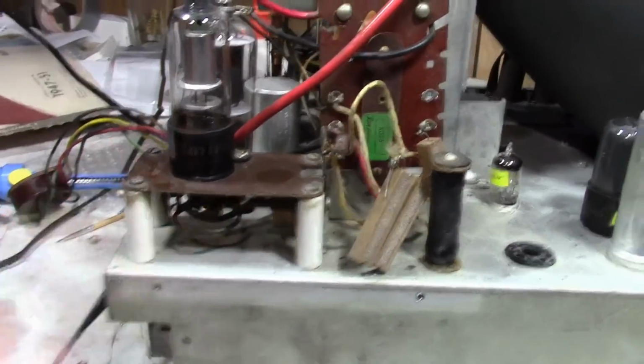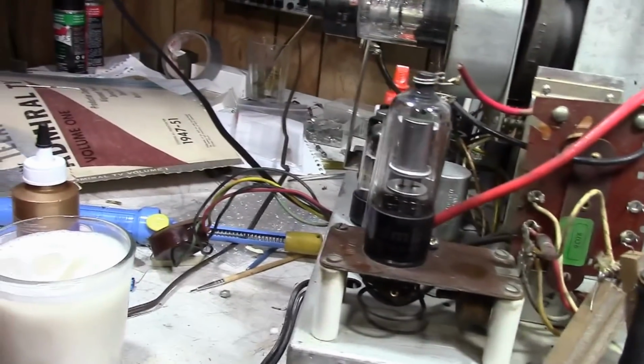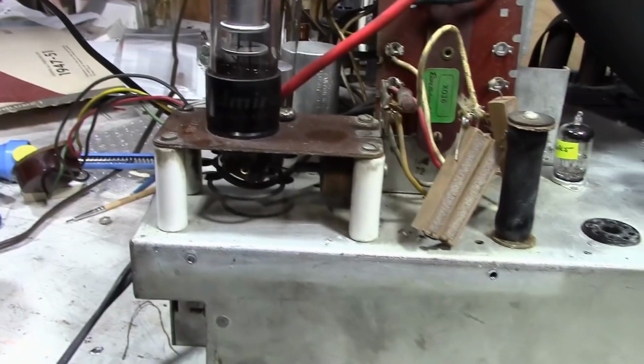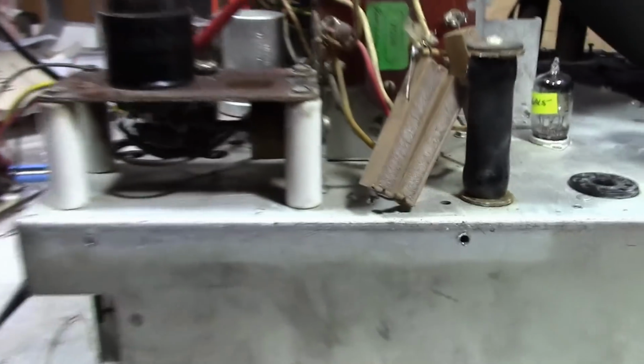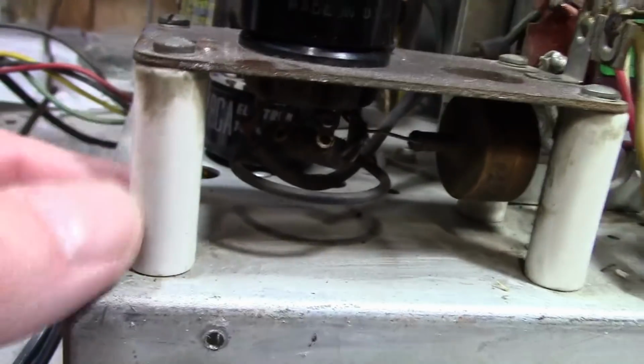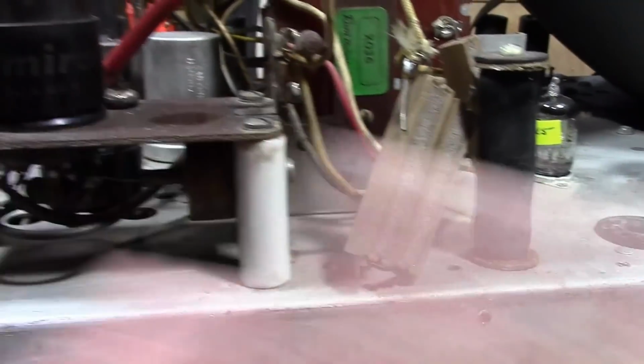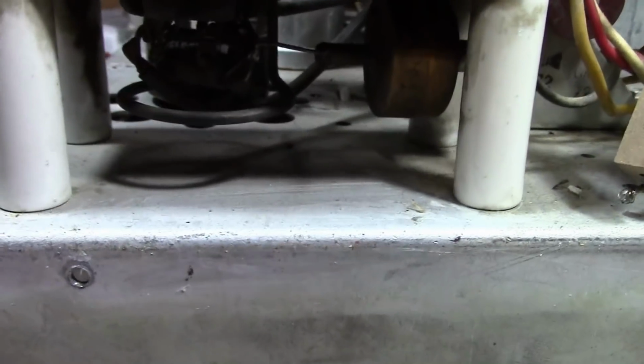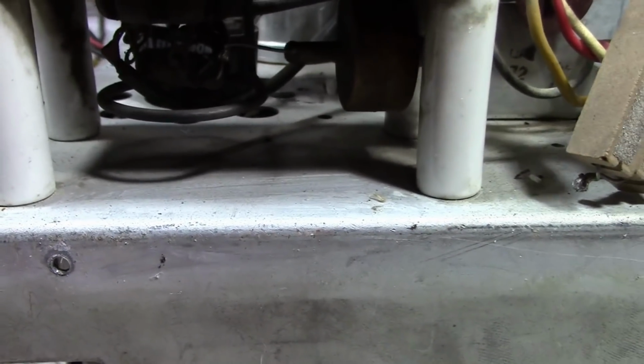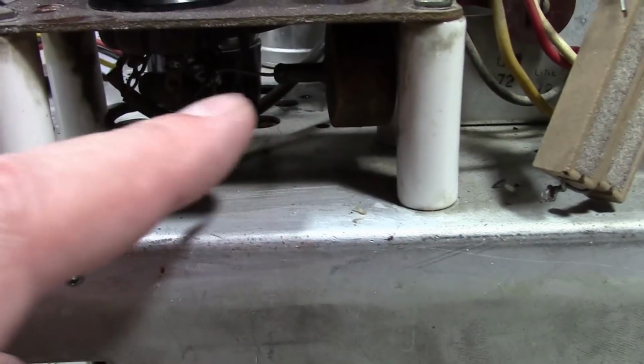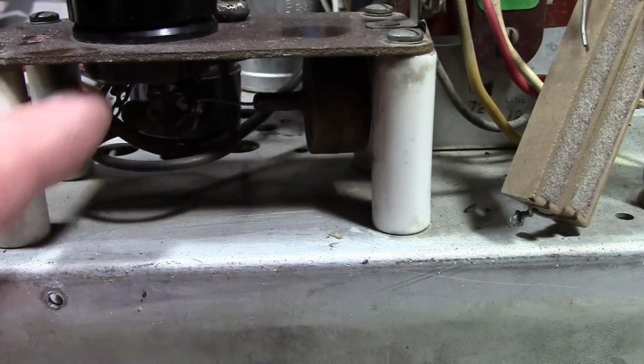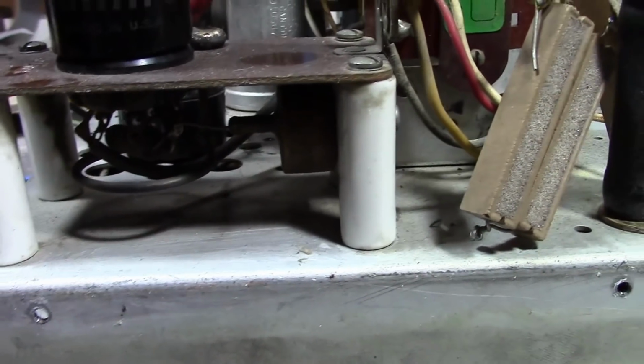Somebody's already done the hard work of cleaning this out, because the high voltage down here also typically attracts a lot of fine dust particles. These pillars are usually not gleaming white ceramic - they're porcelain, usually kind of black, with black soot over everything. That ring down there is called a corona ring - it's connected to the high voltage and keeps everything at equal potential around this area with no sharp edges, to suppress any arcing.